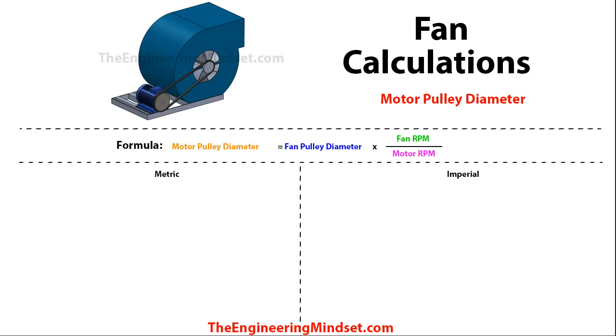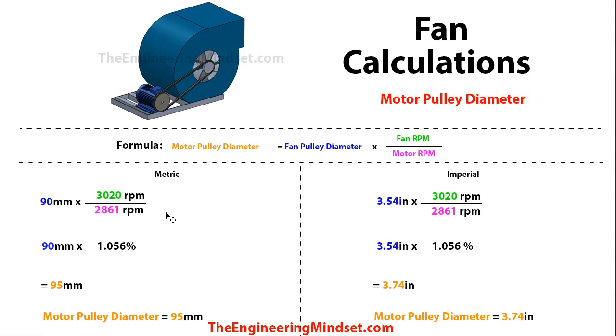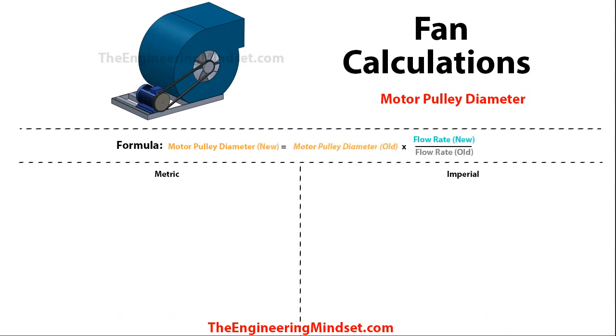Next we can calculate the motor pulley diameter — for instance if a new motor or fan has been installed. The formula is: motor pulley diameter = fan pulley diameter × (fan RPM ÷ motor RPM). Dropping in the numbers — fan pulley of 90 mm (3.54 inches) — the division of the two RPMs gives 1.056, which multiplied by the fan pulley diameter gives a motor pulley diameter of 95 mm (3.74 inches).